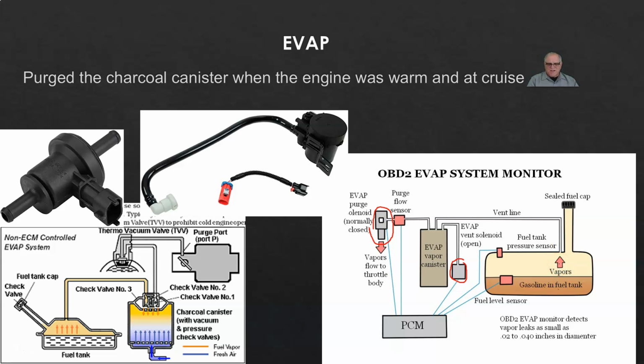We're going to be measuring this in inches of water, not inches of mercury. This sensor is going to tell the computer when the system went into a vacuum. The reason the computer is going to watch the fuel level is because how big this space is, whether the tank is full or close to empty, is going to affect how long it'll take to pull into a vacuum. The computer is going to look at temperature, it's going to look at the vacuum, it's going to look at the amount of time.